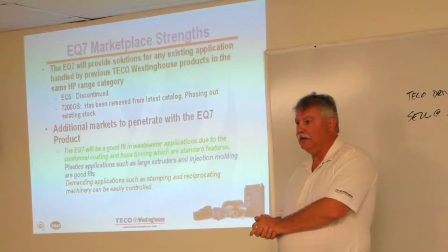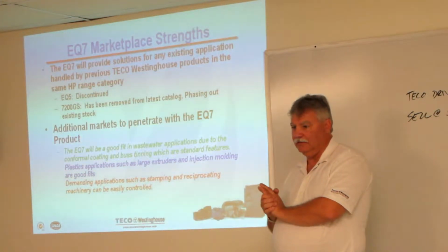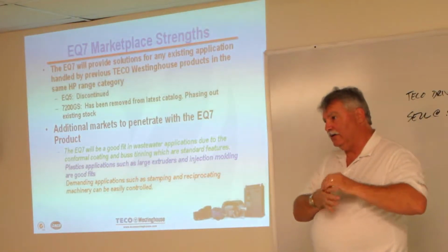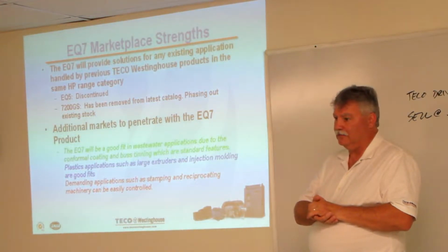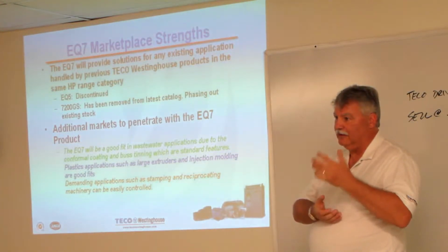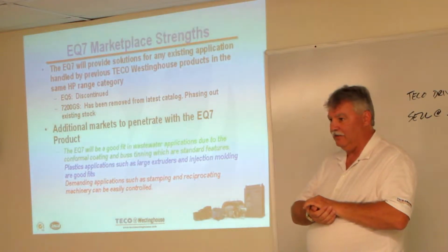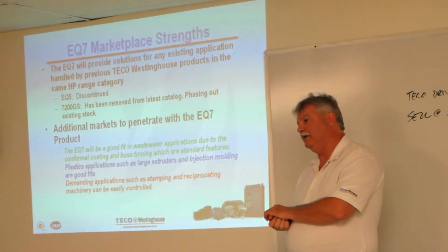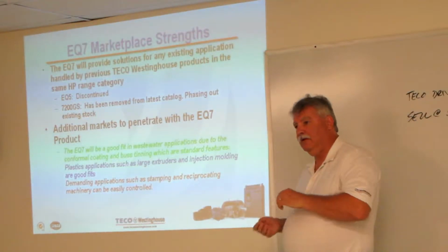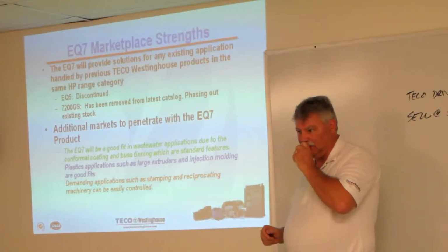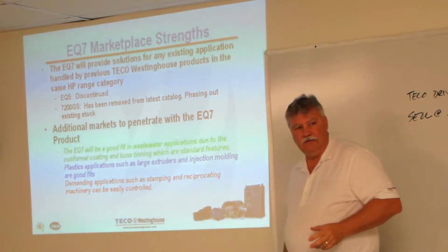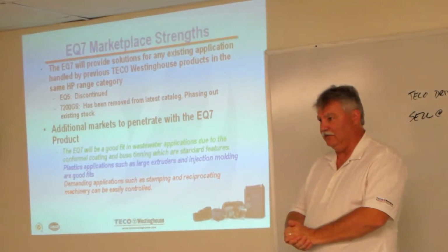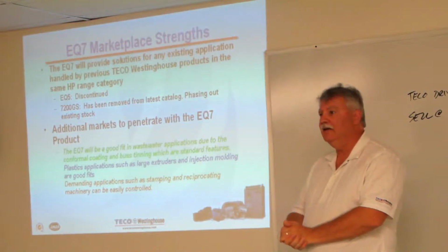Right, and the other thing you have to be concerned about is lead lengths, because if you're running 4 motors, you have to take the sum of the 4 motors' lead lengths into consideration. So that might add some harmonics and other bad issues like ground loop currents or reflected waves. Having said that, this drive is particularly strong at that point. You can go up to 1,300 feet. That's why I started asking about your motor lead distances before you have to consider any sort of filtering, because it's built into the drive itself with the transistors and the technology employed there. Again, part of that 10-year design life.